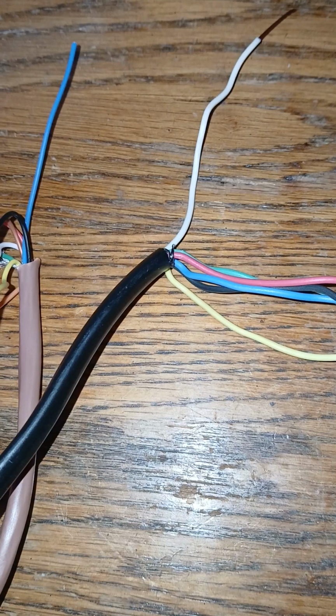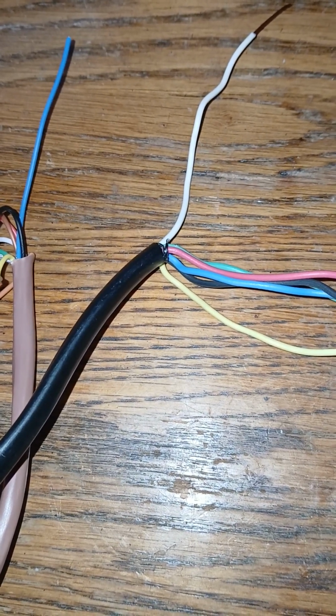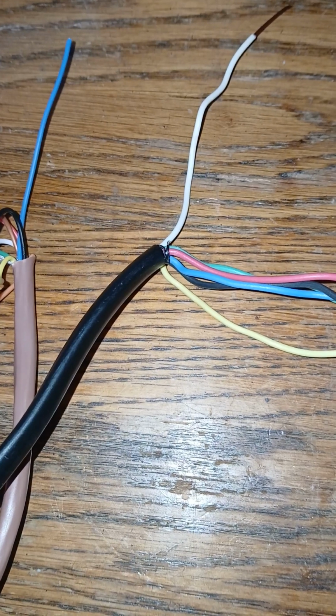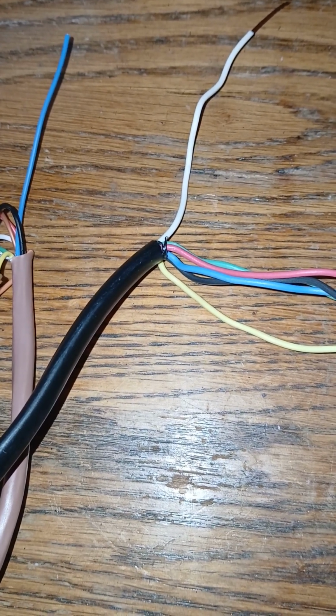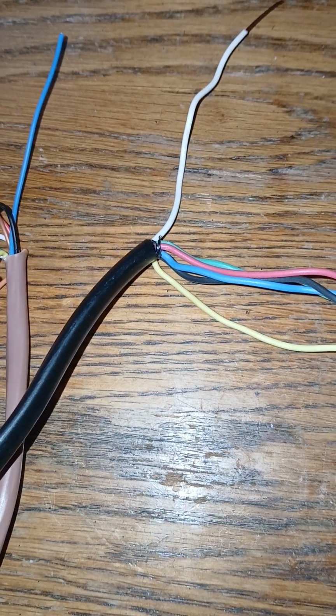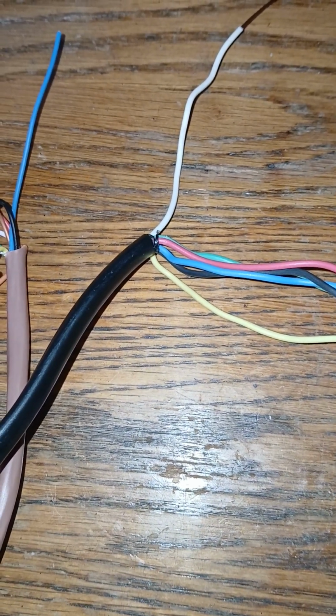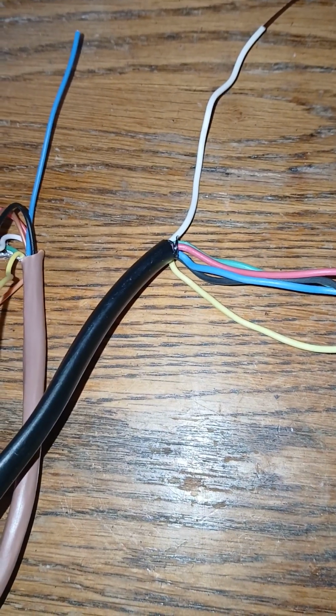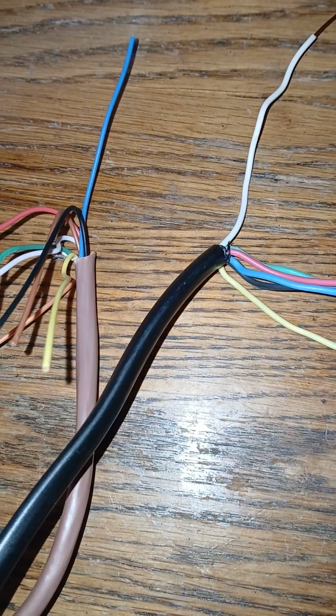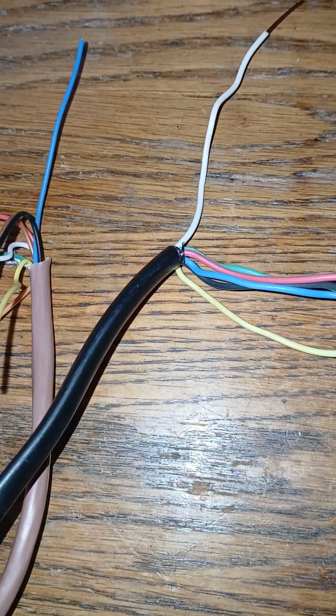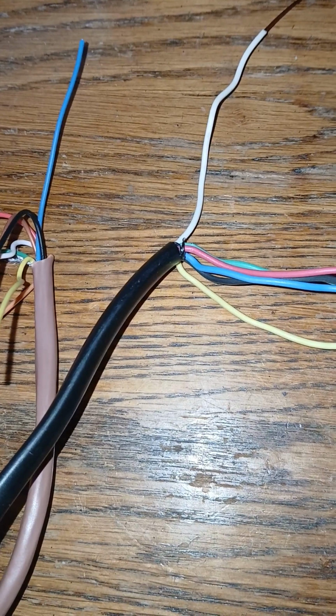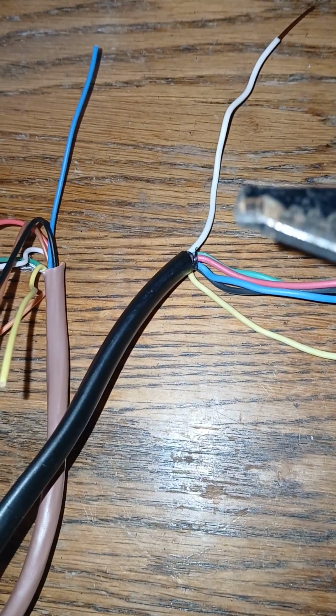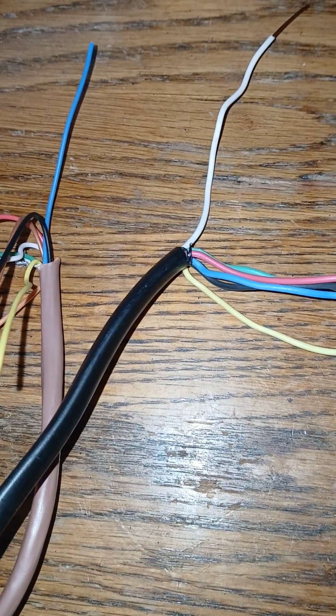The lawn sprinkler system goes through a transformer, and the HVAC system goes through a transformer. The white wire for lawn sprinkler may be considered the common, and the blue wire for HVAC thermostat may be considered the common. So we have two different wires. The rest of the wires in the sprinkler system would be your hot wires, and the rest of these over here become hot after being energized by the red wire.